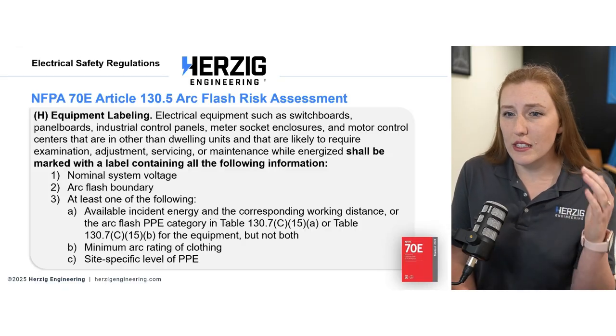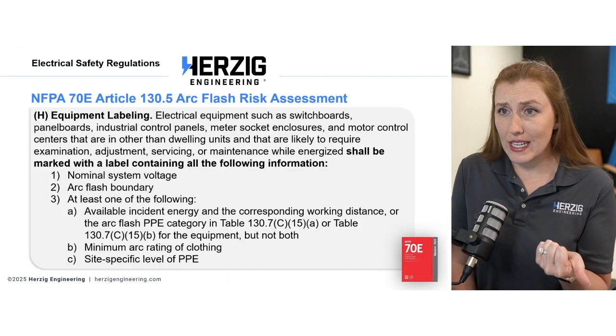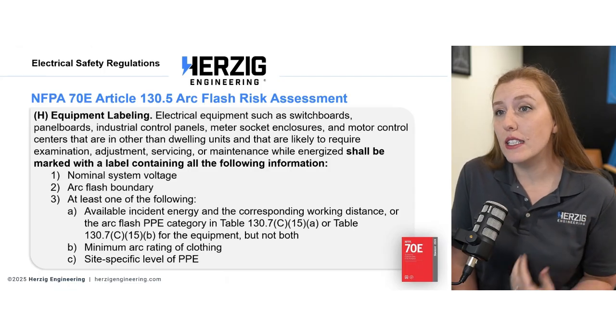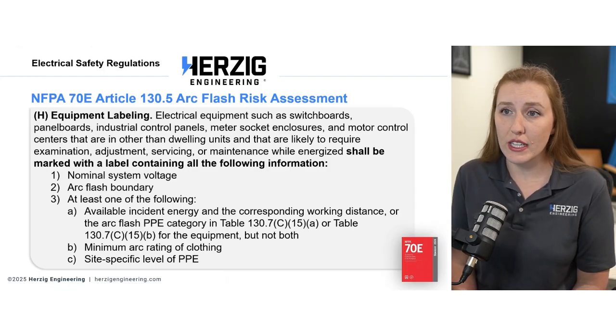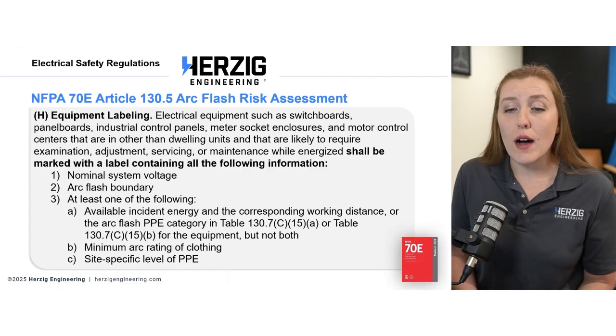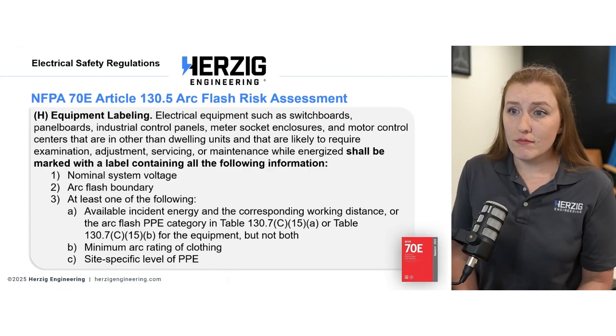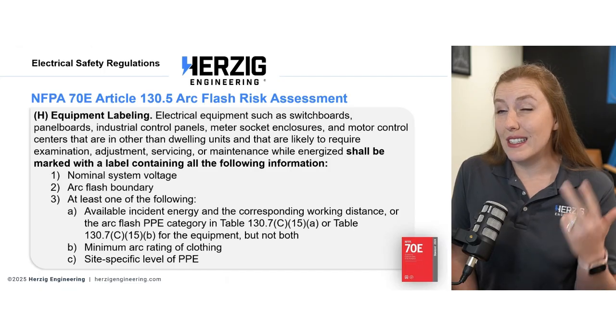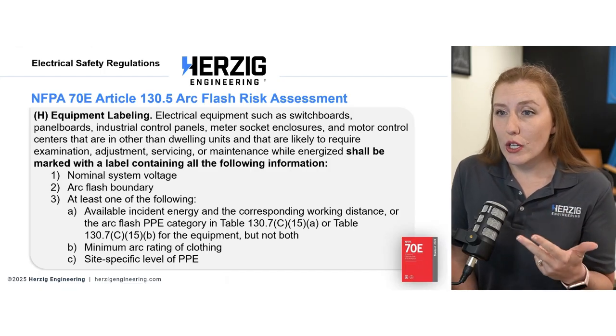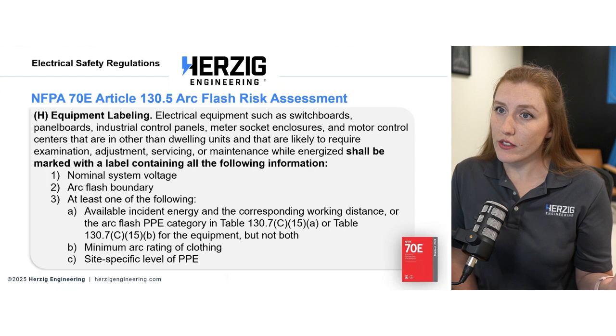A good summary here is, well, what is needing an arc flash study? Anything likely to require examination, adjustment, servicing, or maintenance while energized shall be marked with a label containing the voltage, the arc flash boundary, and some way for workers to know how to protect themselves against the arc flash hazards.